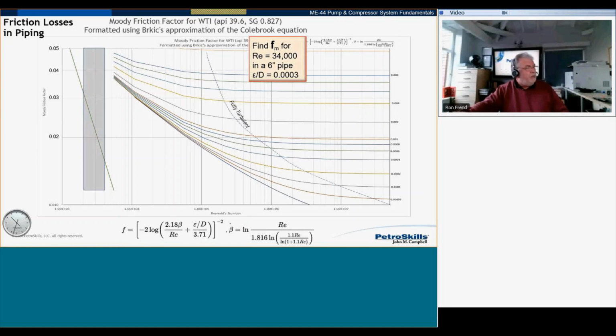Okay, so what we're doing is we've got beta, we're plugging that into here. And what we do is, because we're doing this with different velocities, we get different Reynolds numbers, which is the bottom axis. And what we get is the Moody friction factor. But notice each of these curves are for a different relative roughness. So let's just do a quick example here. We're going to find the Moody friction factor for a flow that's got a Reynolds number of 34,000. So there we are, this is 34,000.